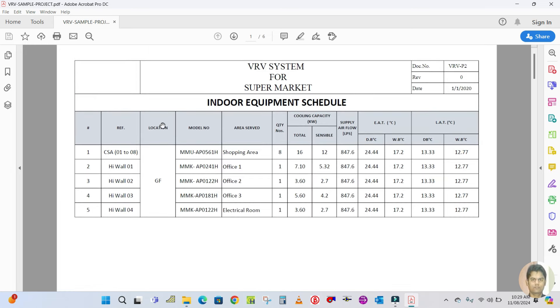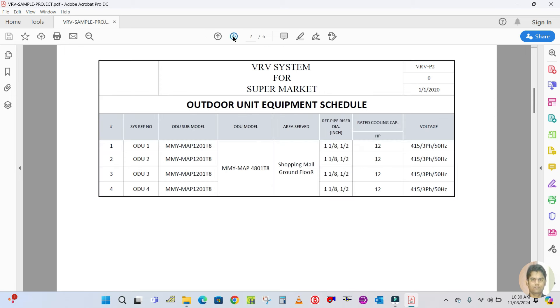This is a VRF project. The first phase shown is the indoor unit equipment schedule. In the schedule you can see the serial number, reference location, model number for the indoor unit, the area which the unit has to serve, quantity, and capacity given in kilowatt — total capacity and sensible. Then supply air flow in liters per second, and EAT which is the entering air dry-bulb and wet-bulb temperature entering the machine, and the leaving air temperature.